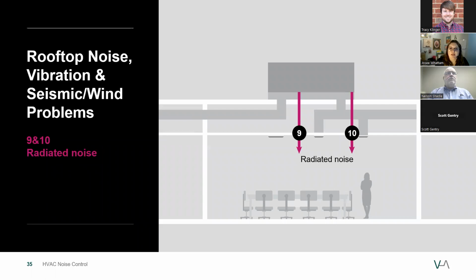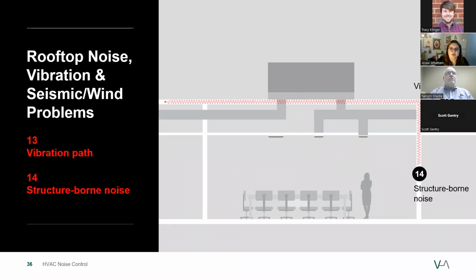The next noise path is radiated noise. So this is noise from lightweight construction of the unit or the building transmitted through the ceiling space directly. This could also be noise from a piece of equipment located in a mechanical room and radiated to the occupied space next door. This usually is low frequency noise problems, which are difficult to attenuate. And the last noise path is vibration or structure-borne noise. Structure-borne noise created by vibrations coming from an RTU's fan, compressors, air through the filter bank or the casing, etc., is some of the worst noise problems to have. They're extremely hard to diagnose, and occupants have a much lower tolerance for these kinds of problems. An additional issue is that the heavy vibrations can lead to damage to the equipment and potentially the structure.